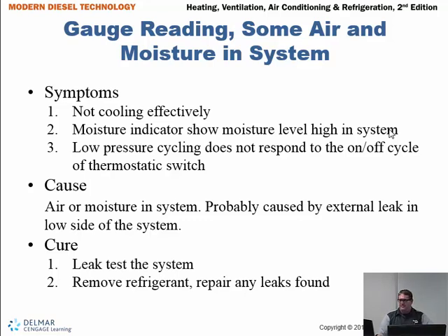Now we've talked a little bit about that sight glass going away, not being the same kind of tool that it was back in the day. A little bit hard to read, some room for interpretation there. Low pressure cycling does not respond to the on-off cycle of the thermostatic switch. So as you're looking at that thermostatic switch, make sure that everything coincides and is responding correctly.